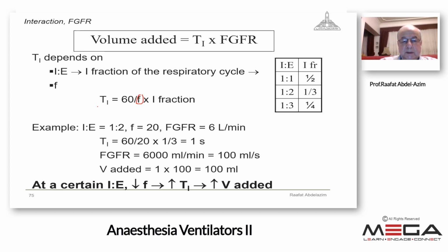For example, if the frequency is 20, the cycle time will be 60 over 20, which is 3 seconds. To make it easier, forget about the fraction now and calculate the inspiratory time. If the rate is 20 and the I:E ratio is 1:2, the respiratory cycle time is 3 seconds. If the ratio is 1:2, so the inspiratory time is 1 second.